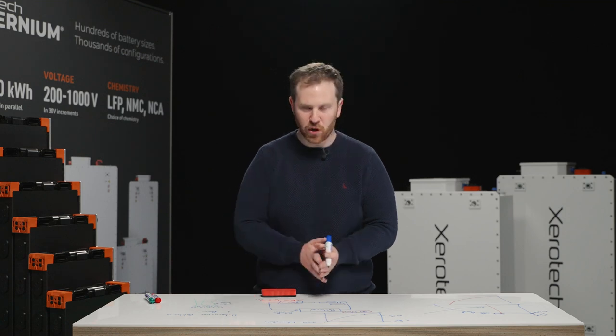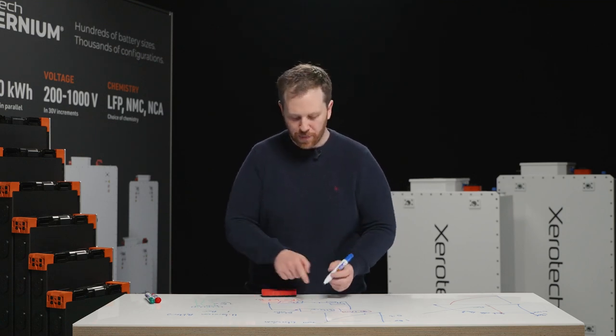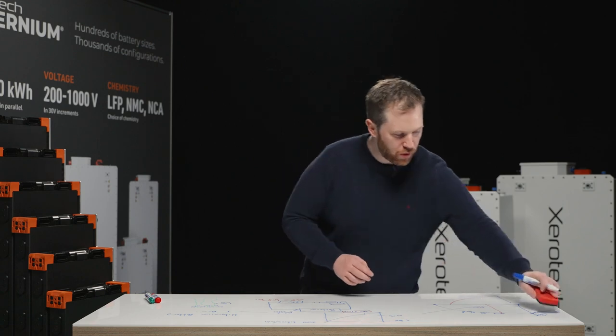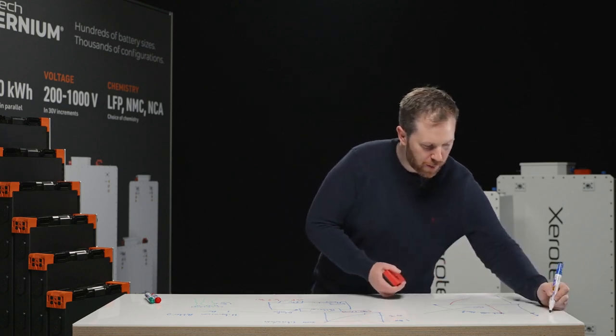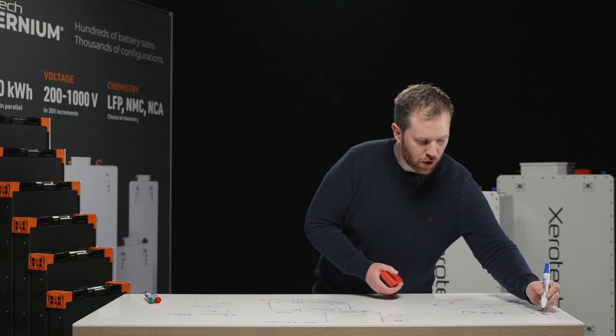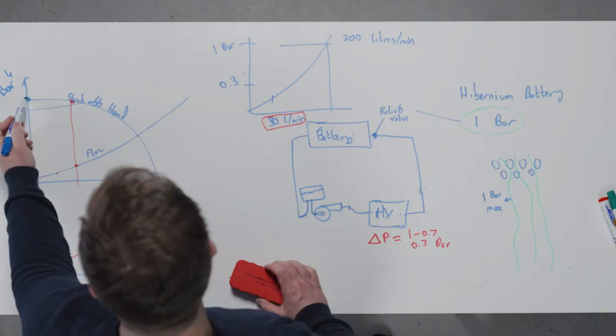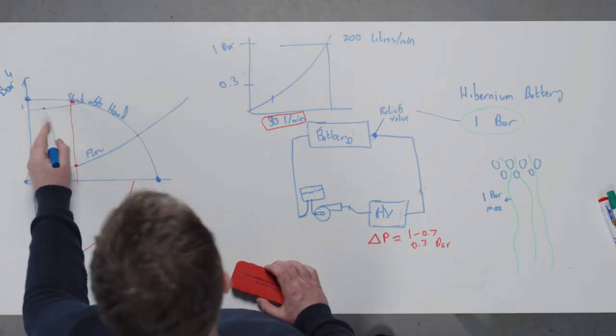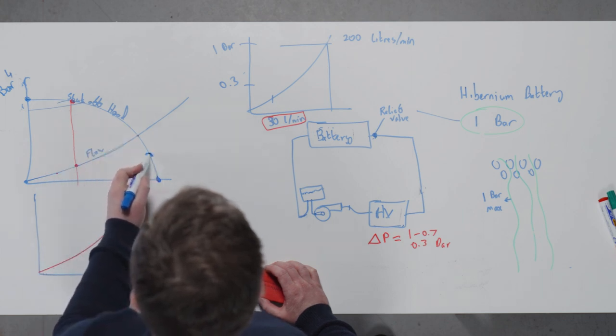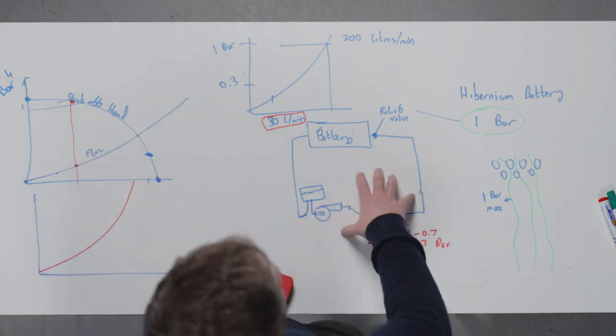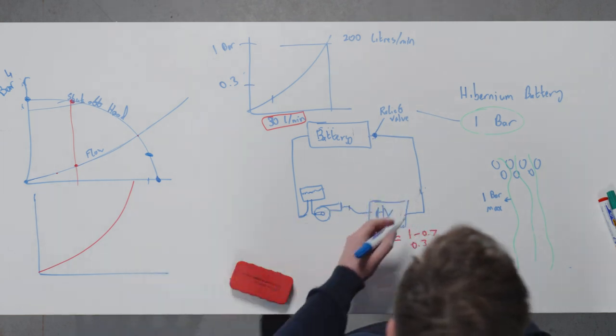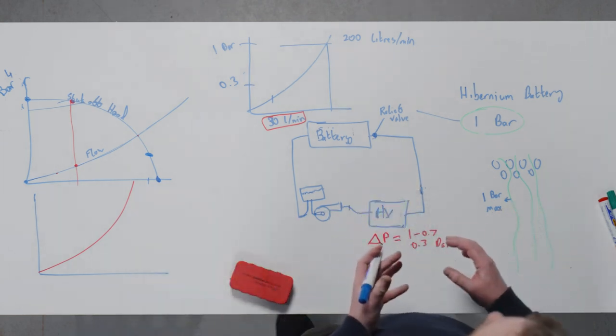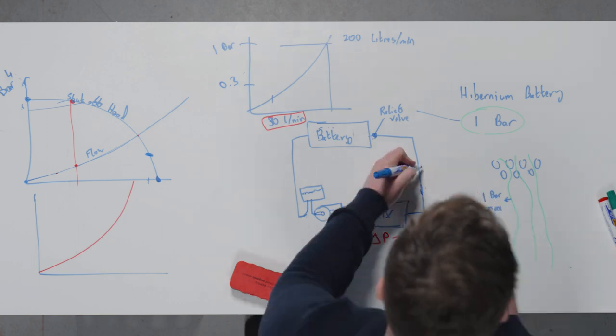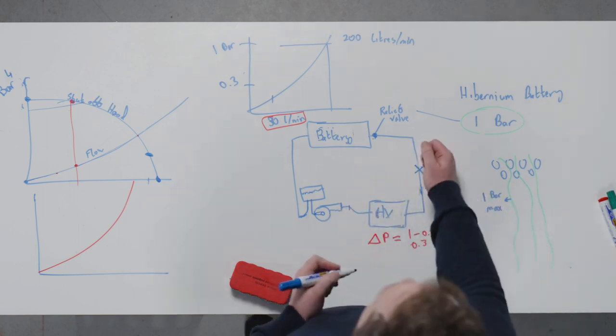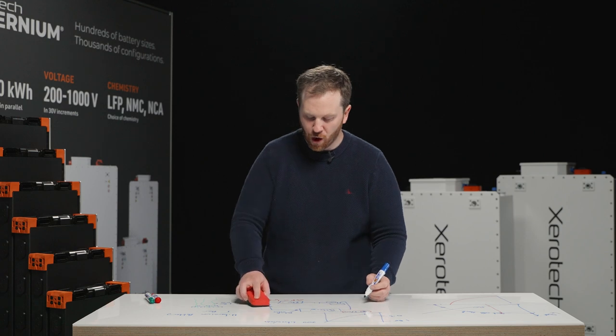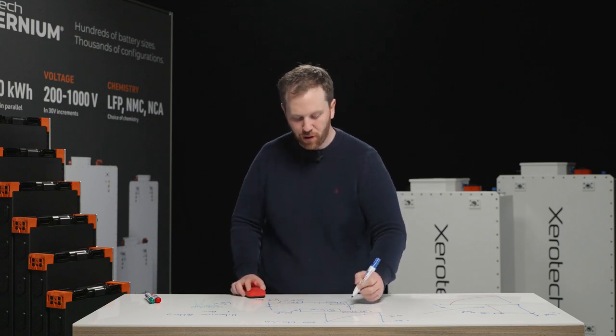In a real system, especially larger systems with multi-packs, this pump might be able to go to 4 bar or more. Now, we never expect to be operating up in this part of the curve. You probably expect to be operating way down here, developing high flow rate with negligible pressure drop. But what can happen is if there's a mistake, an accident, or a commissioning error somewhere in the system, we shut a valve in the wrong place. And worst case of all, we shut it after the battery pack.